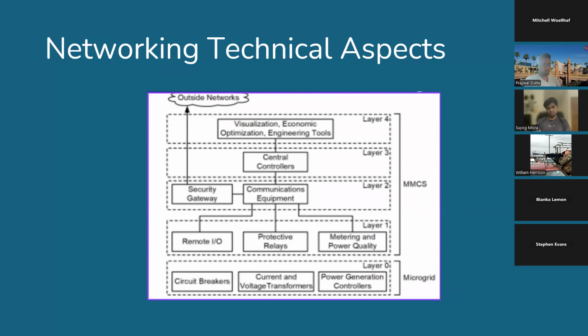Layer 0 in the image includes physical power devices like circuit breakers, CTs, VTs, and power generation controllers. This is considered the foundation of our microgrid system. These devices don't communicate. They act based on inputs or direct control from the higher layers. Layer 1 includes protective relays, remote IOs, and metering systems. Intelligent electronic devices are the bridge between raw electrical data and the control system. They take real-time measurements, make decisions based on pre-programmed logic, and send data upstream.